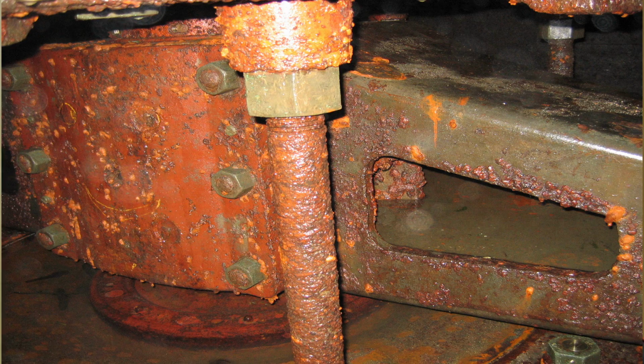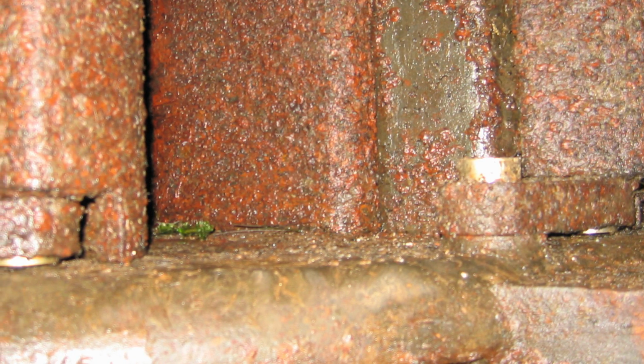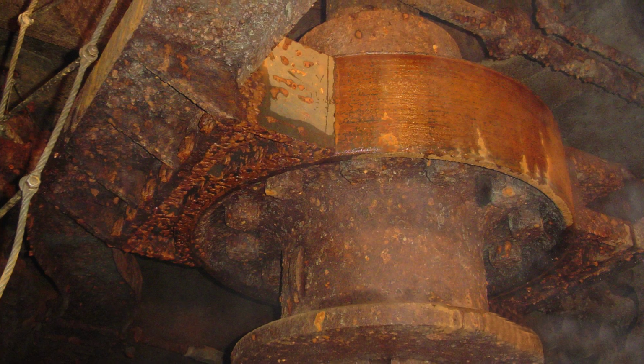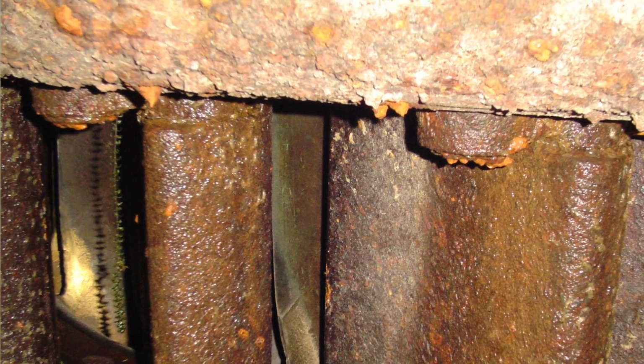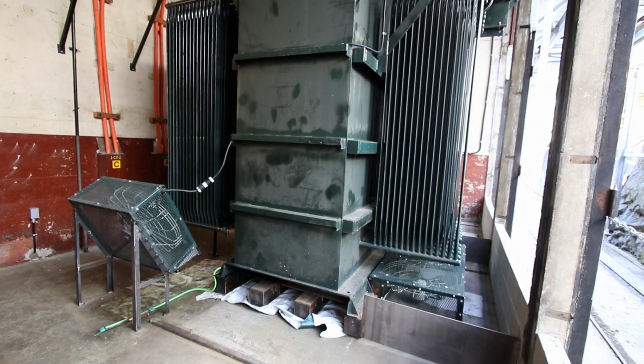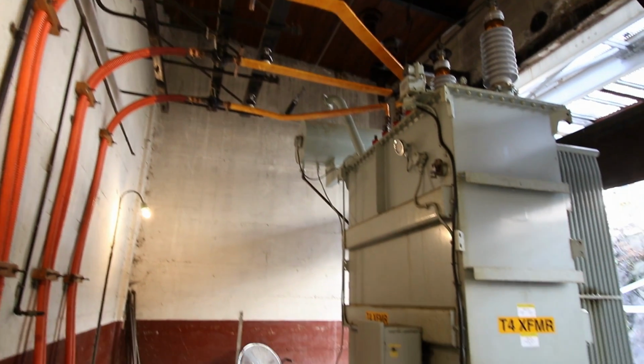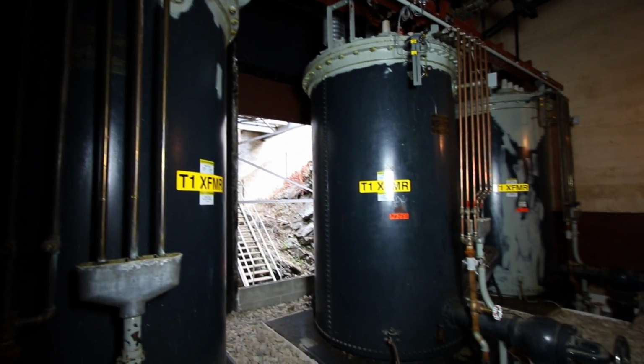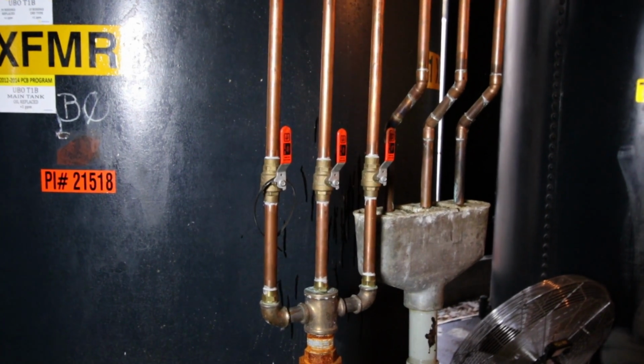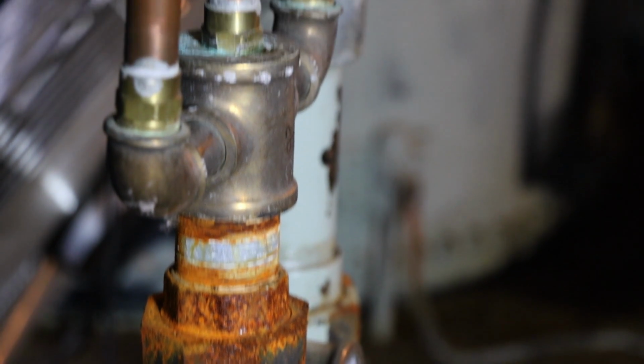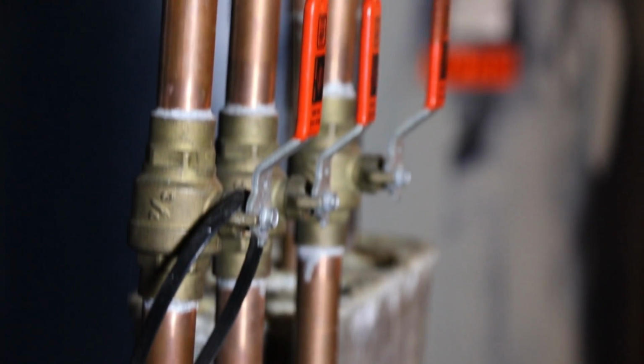If you were to look inside these older units, you'd see that the internal components are very heavily corroded and clearly showing their age. This has a direct impact on our ability to control them. The 4 unit transformers are from a variety of manufacturers and are all completely different in design and age, the oldest being 80 plus years old. This older transformer is a 3 separate single-phase design that is water cooled, and with its failure history, replacement has been recommended. It's obvious that the systems and equipment at the Upper Bonnington old plant are end of life. In my opinion, the recent failures prove that the units are unreliable and that they're going to continue to expose our workers to safety hazards, which I believe is definitely avoidable.